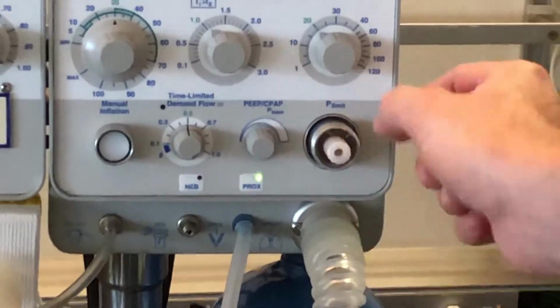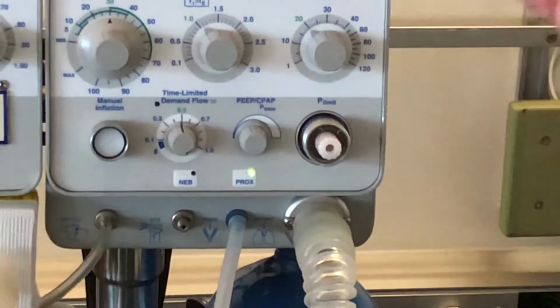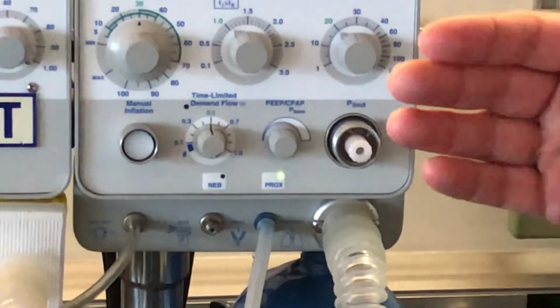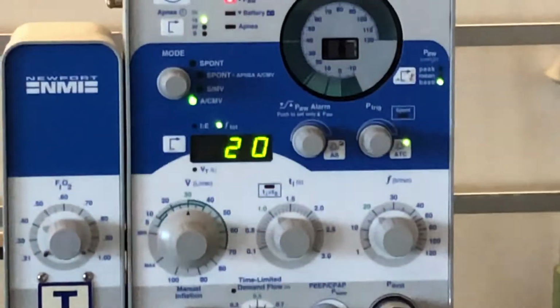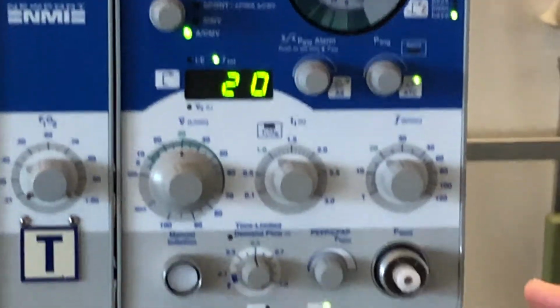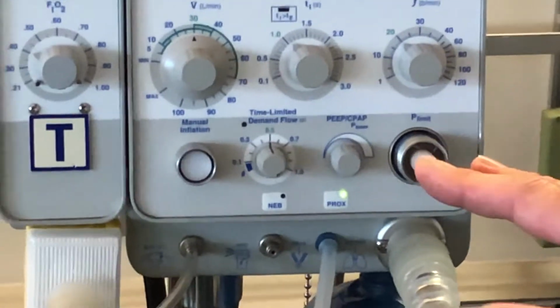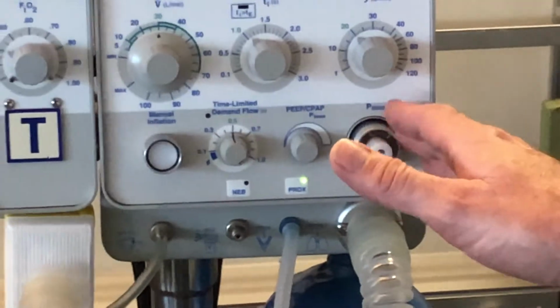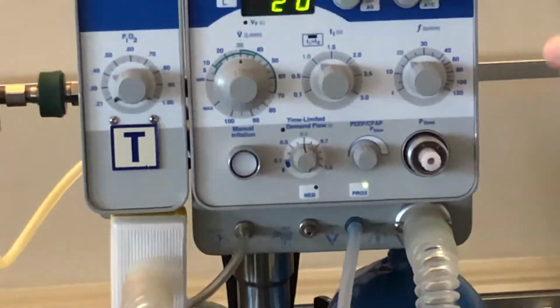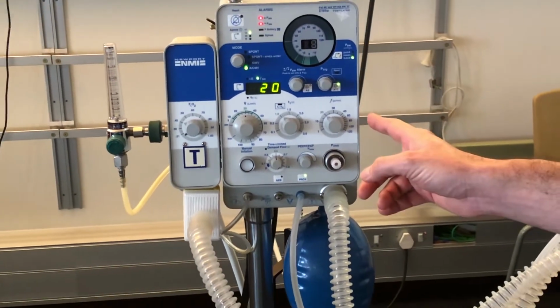And then the last setting we've got here is the ultimate upper pressure limit that the machine will deliver, and that's usually set by our technicians in our ventilator store. And I'd suggest to all of you that you don't tamper with the setting of the upper pressure limit unless you really know what it is you're doing with the ventilator.